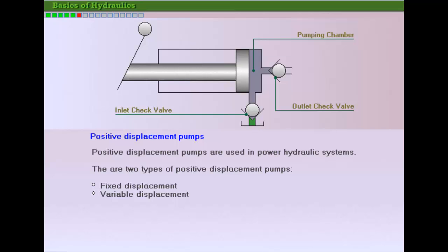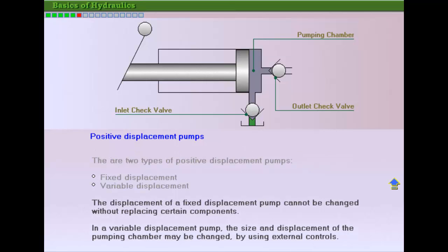Positive displacement pumps are used in applications where a confined fluid is used as a medium for power transmission under pressure. Positive displacement pumps are of two types, fixed and variable displacement pumps. In a fixed displacement pump, the displacement is constant and can be varied only by replacing certain parts within the pump.